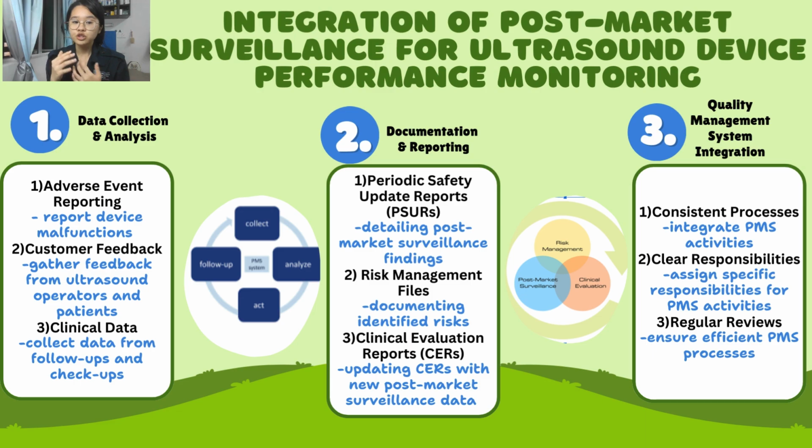Secondly, ensure thorough documentation and reporting by submitting regular periodic safety update reports, in short form called PSURs, to regulatory authorities, and maintaining an updated risk management file documenting identified risks and mitigation measures, and updating clinical evaluation reports, or in short form CERs, with new surveillance data to ensure the continued safety and performance standards. And also, it can be simply explained using a diagram as shown in the slide.